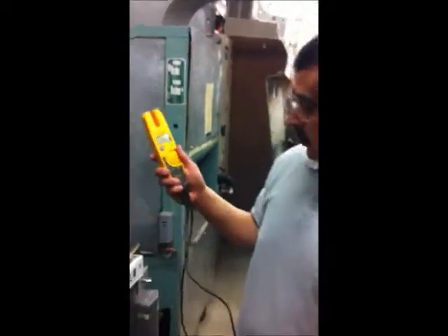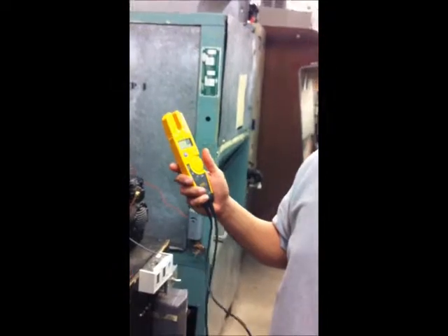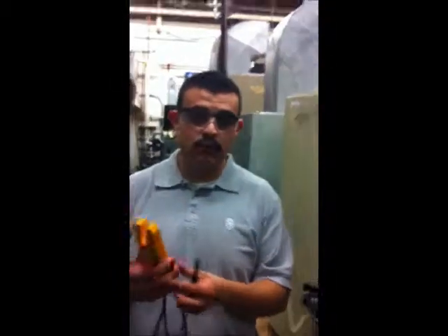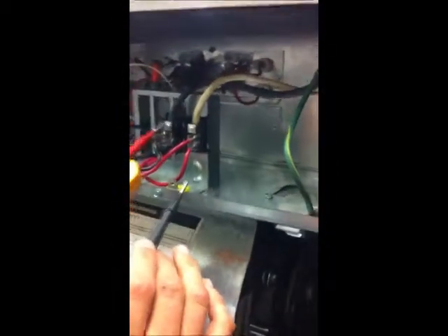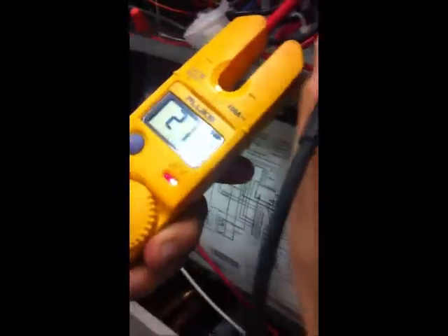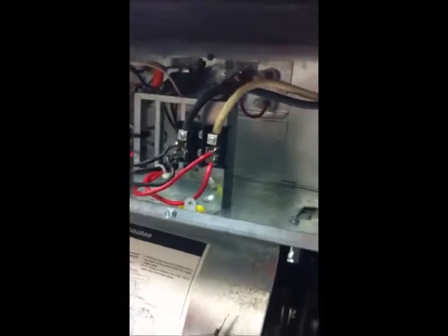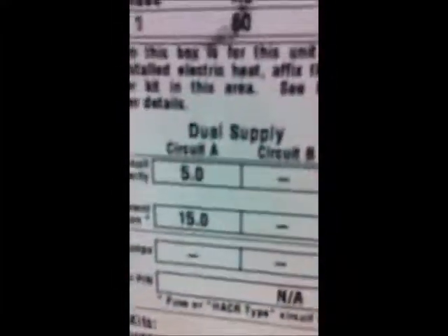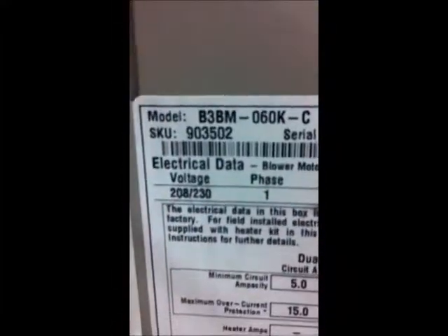Okay, so now that we have power, we're going to grab our Fluke meter and we're going to turn it to volts, and then we're going to see if we're getting line voltage in. So I'm going to put this in here. Then I'm going to measure for voltage. And we have ourselves 210 alternating current. So it means that we do have power to the heater. And we can compare that, because this data over here says it's a 208, so it has 2 volts more, so that's a good sign.